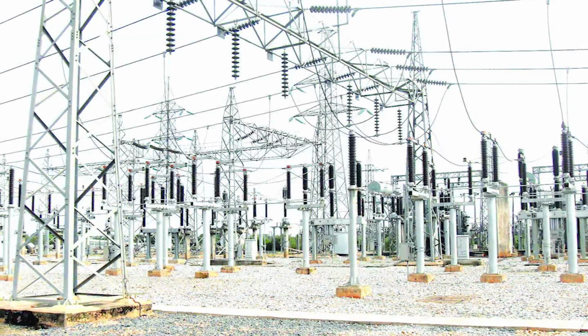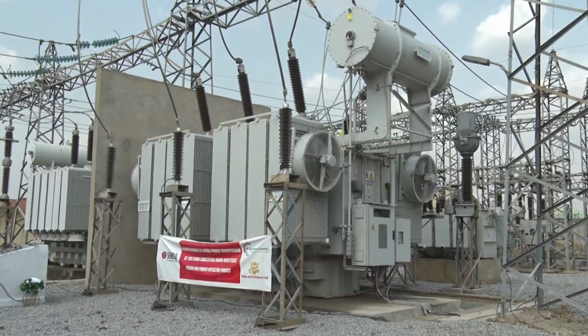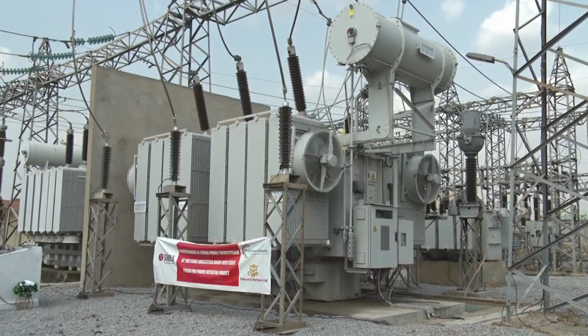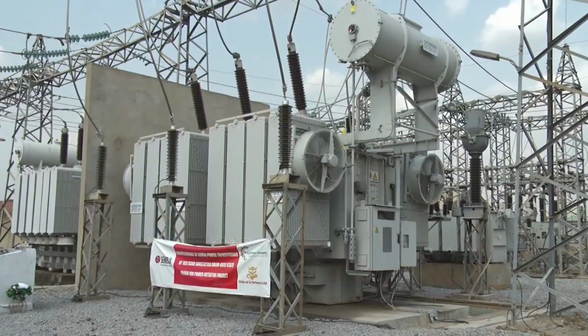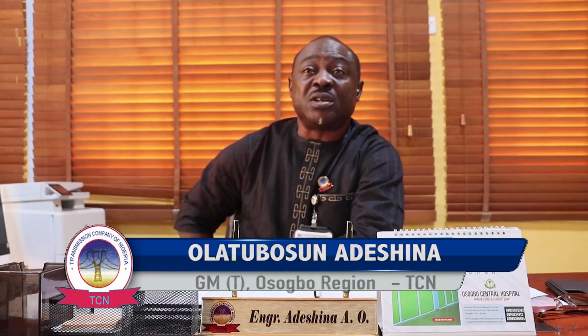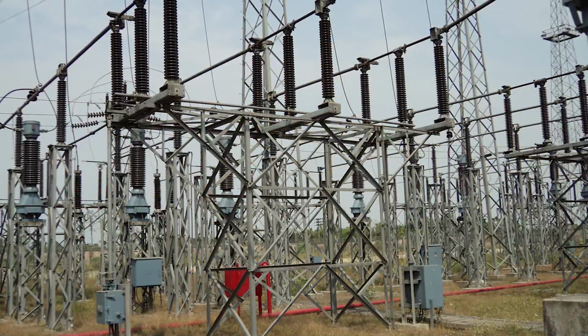At Chagam, we commissioned 2 60 MVA transformers, and this has increased the capacity of that station from 60 MVA to a 180 MVA station. Another project, aside transformer installation, we've been able to execute reconductoring of transmission lines, and I can mention a few, particularly the Ayede LA 132 kV line and the Ayede Jericho 132 kV line. This has greatly increased our wheeling capacity to Jericho TS, to Ibadan North, Susayi, and some other stations along that corridor.